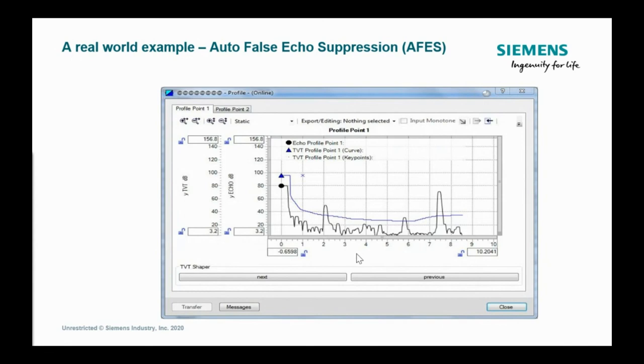And what auto false echo suppression does is it allows you to manipulate this TVT curve. It's three steps. You'll see a slide here. They actually make it four steps, but it's really three. What you do is you put the process in its lowest level, which it was, and then you subtract about a foot, foot and a half from that. So let's assume this was down here at 25 feet. What we did is we said, okay, we're going to enter a distance of 23 and a half feet.